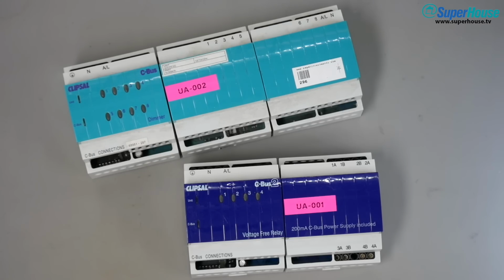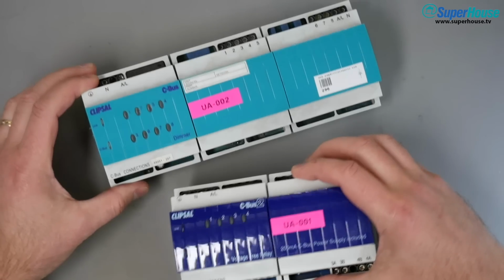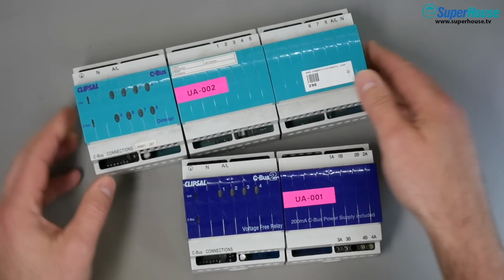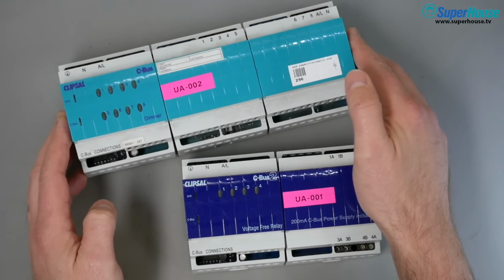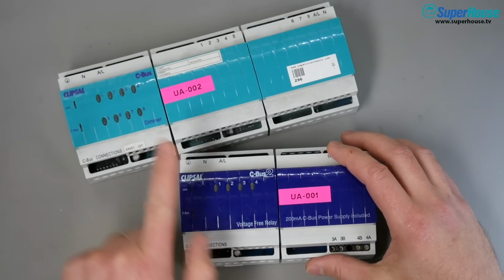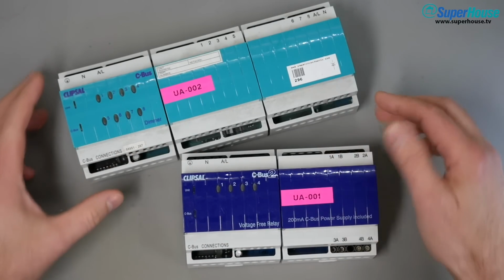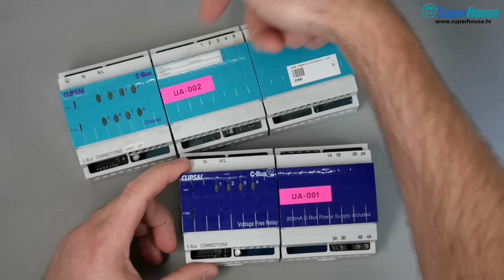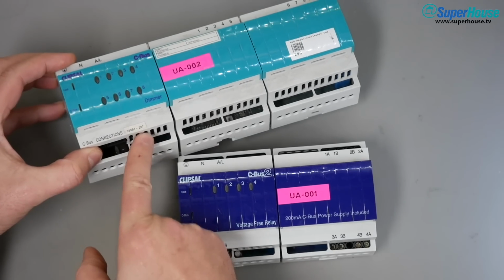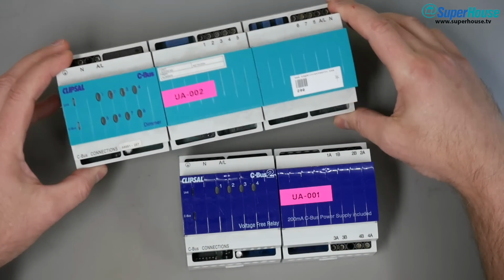Here in Australia, the dominant professional home automation system is Clipsal CBus, and it works in exactly that way with a star topology. Inside the automation switchboard, there are modules, which typically are either a relay output or a dimmer output, and the loads are wired back to them. And then the automation system can send commands to those modules to turn the loads on and off.